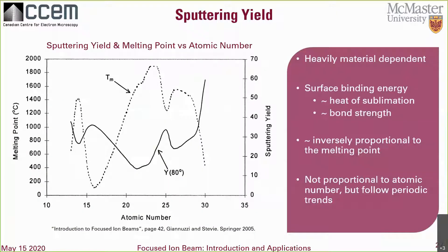Sputter yield describes how fast we are removing atoms from the material — this is your relative milling rate and is heavily material dependent. With different materials, you can more than double your FIB working time. The yield is governed by the surface binding energy, which you can approximate by the heat of sublimation and bond strength. For something more familiar, sputter rate is inversely proportional to the melting point. As you can see in the plot, it's not proportional to atomic number but does follow general periodic trends.